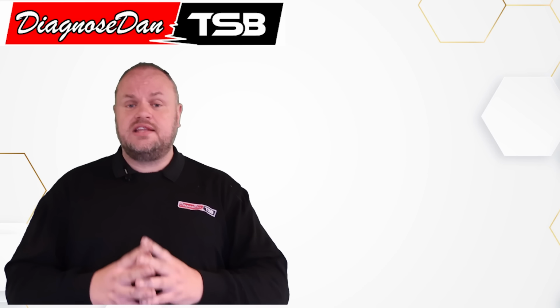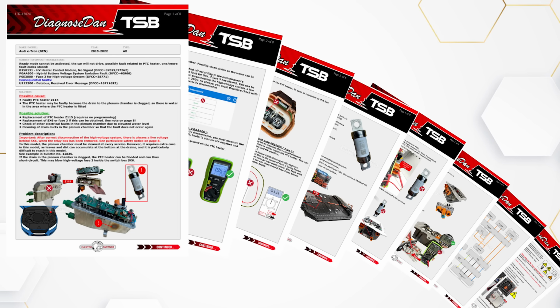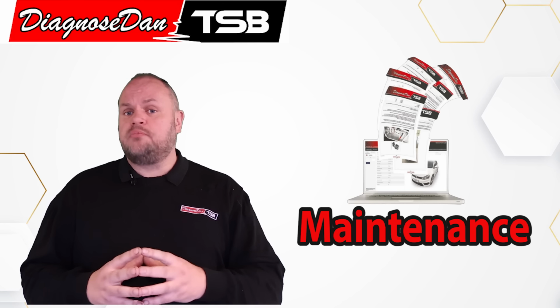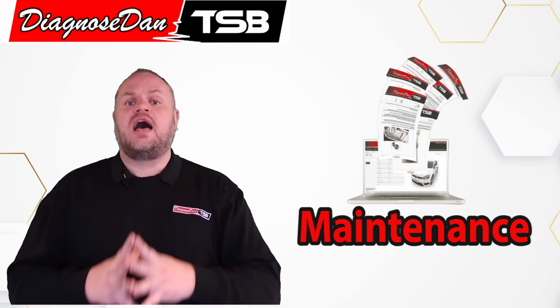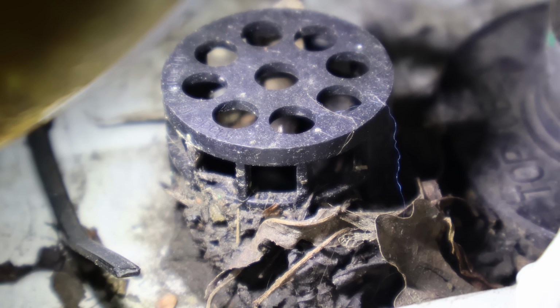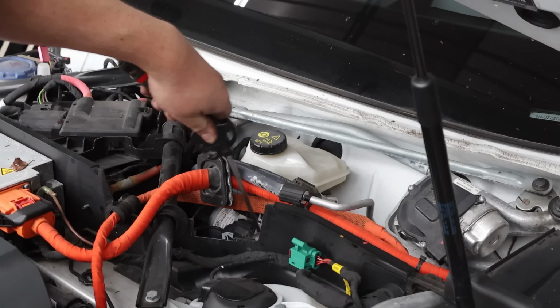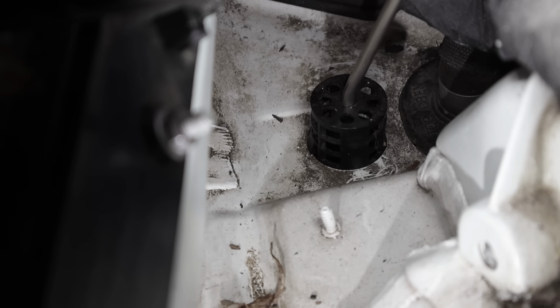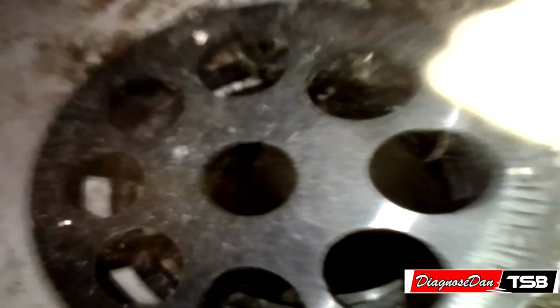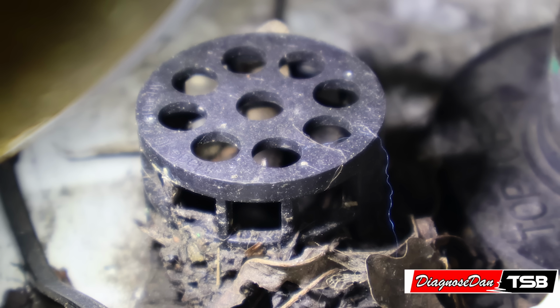Of course, we made a DDTSB bulletin on the blown high voltage fuse, and this bulletin contains more information than you will ever find in the OEM documentation. We also made a maintenance bulletin available that highlights the importance of keeping those drains in the plenum chamber clean. It really makes a difference. It's only a 15-minute job, but it can avoid you from replacing very expensive parts.